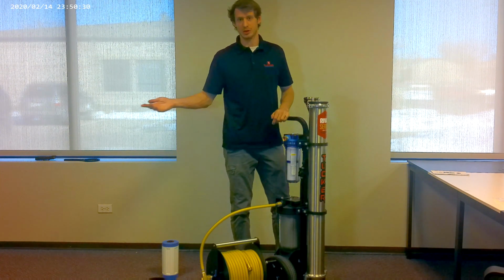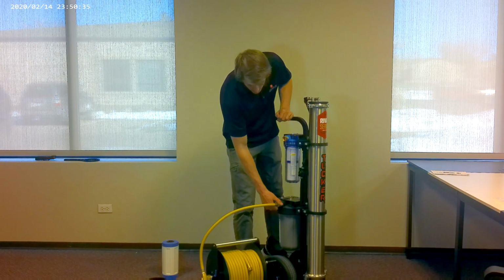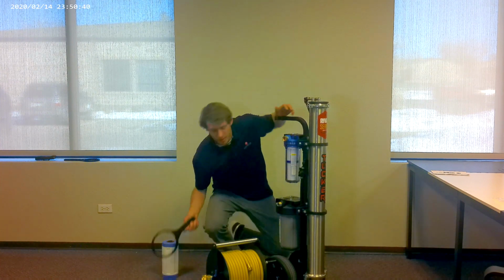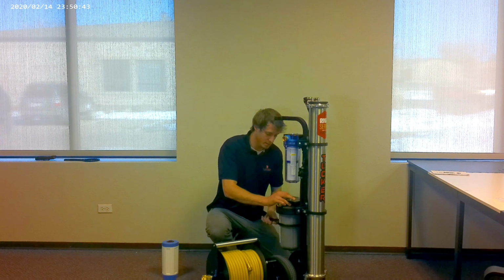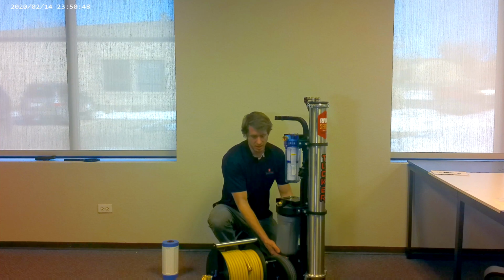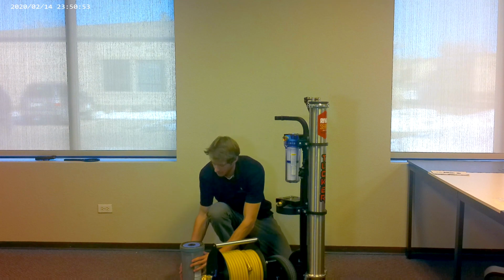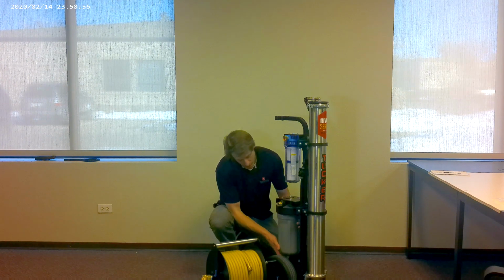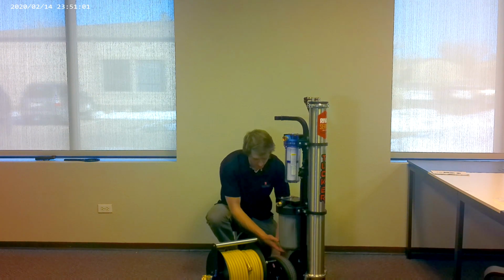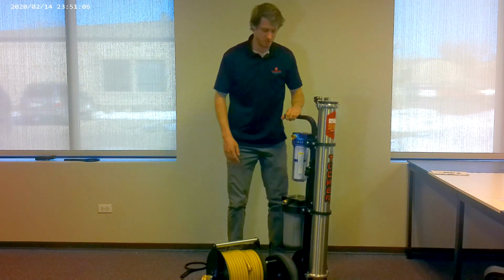After that, we're able to turn off the tap source, disconnect the hose lines, and reinstall the DI. This housing is going to be full of water. Just be ready to dump this out. Reinstall your DI. And now your cart is ready for 2 more weeks of storage.